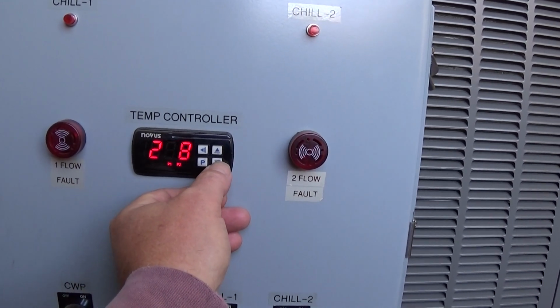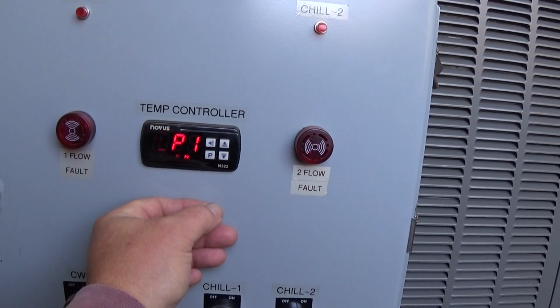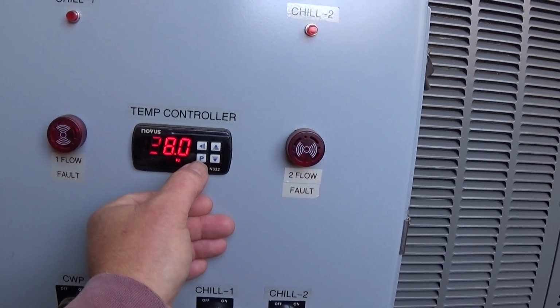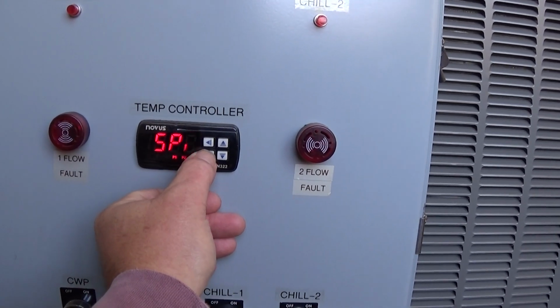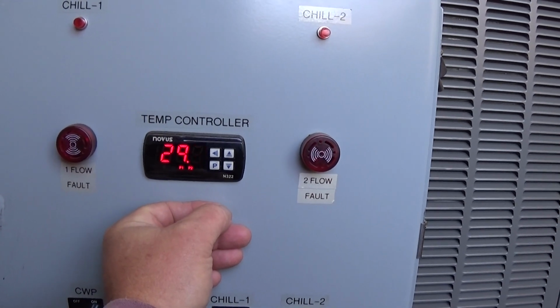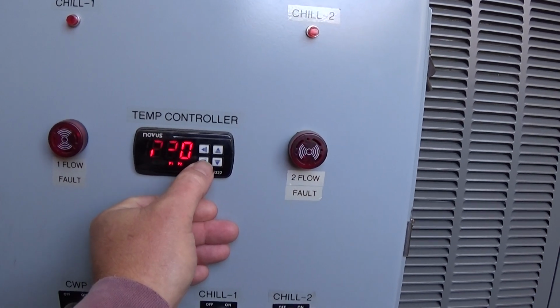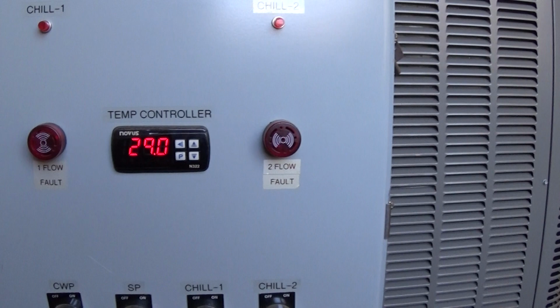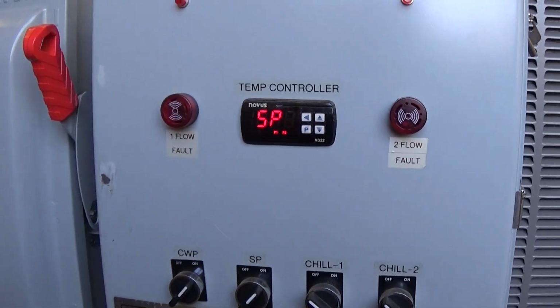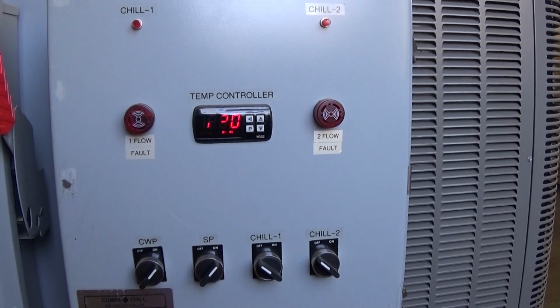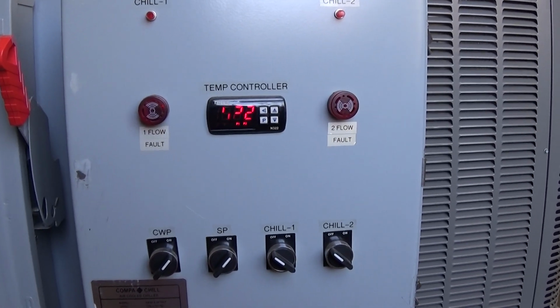It goes back and forth. I have it set at 28. To adjust it, you just go up and down. Press set point 2, or the other circuit. I just happen to have that at 29, so you can see the difference. And then if you hold and press P for 5 seconds, per the manual, you go into other parameters. The only other parameter you may want to change is the hysteresis, or the differential. They're both set at 5 degrees right now.